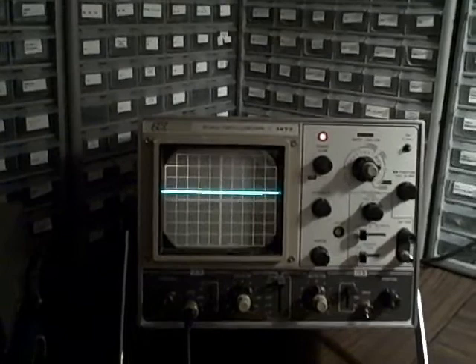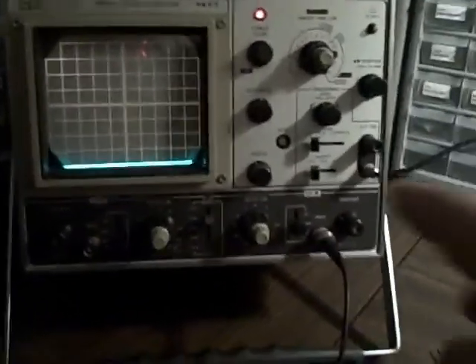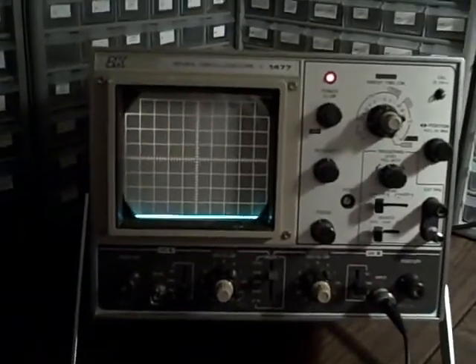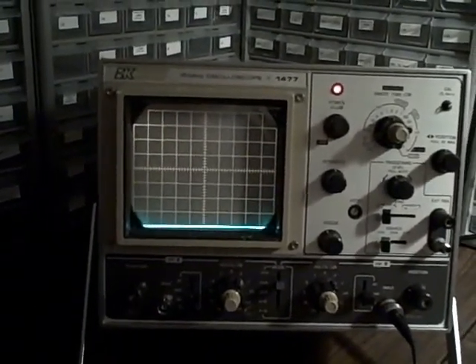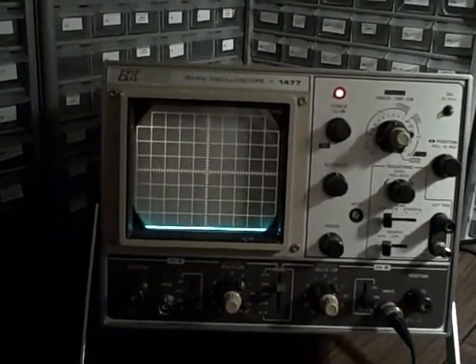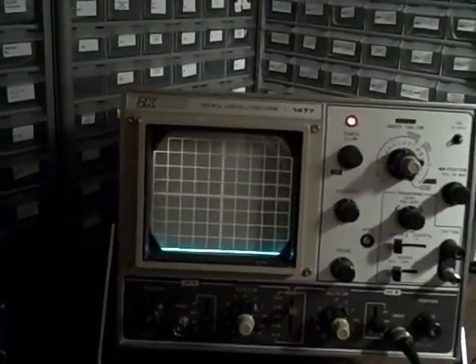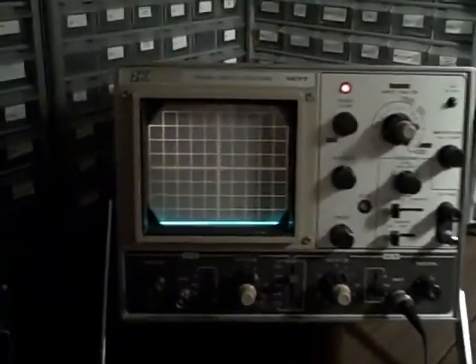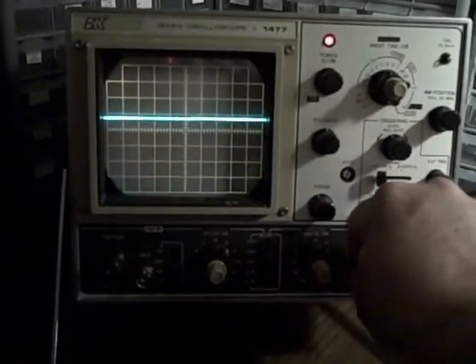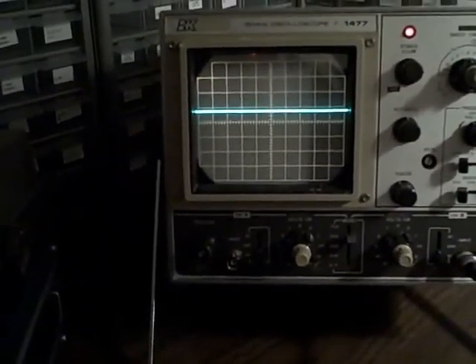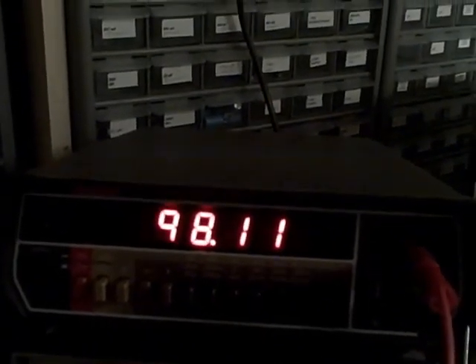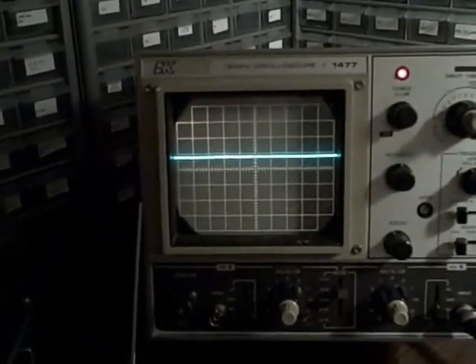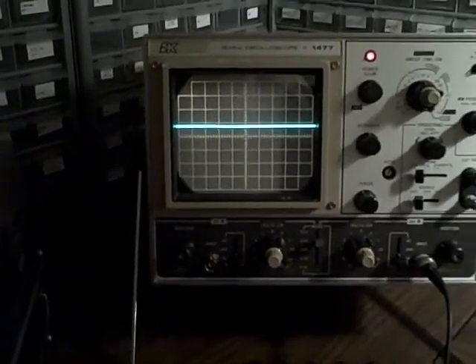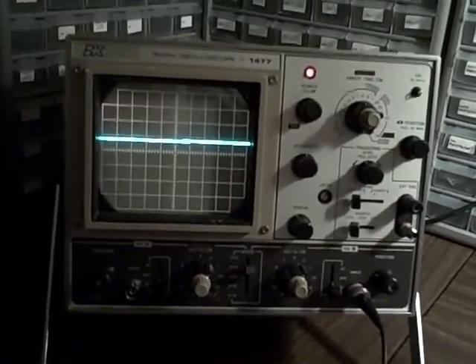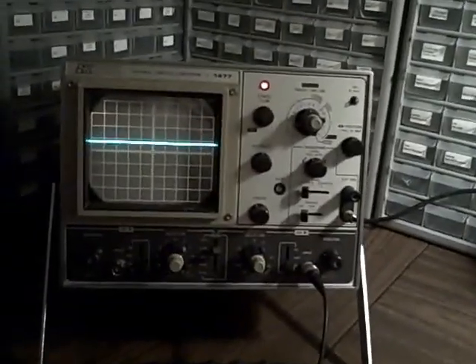Let's go ahead and switch to channel B. Okay, as you can see, we are now connected up to channel B. Since we are already hooked up to the Heathkit, we're going to start at the opposite end of the range switch. We're going to start at 20 volts per centimeter, or per division. And we'll go ahead and put ourselves online. Right now we've checked our ground point, and we see we've risen 4.8 divisions, and we are getting a reading of 98.11 volts. The 98 volts would be 4.8 divisions, so this is reading accurately on the 20 volt per division line.